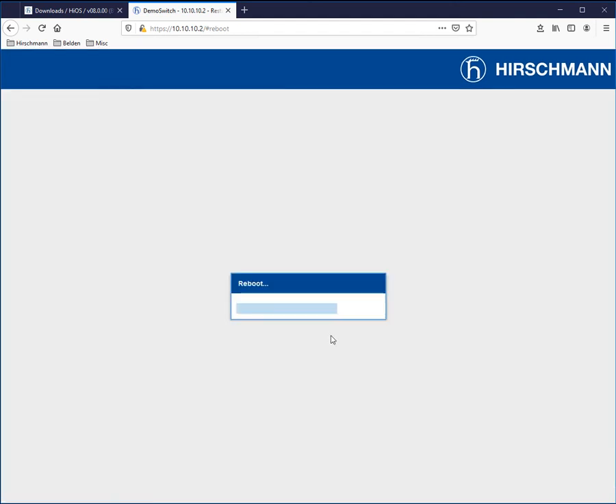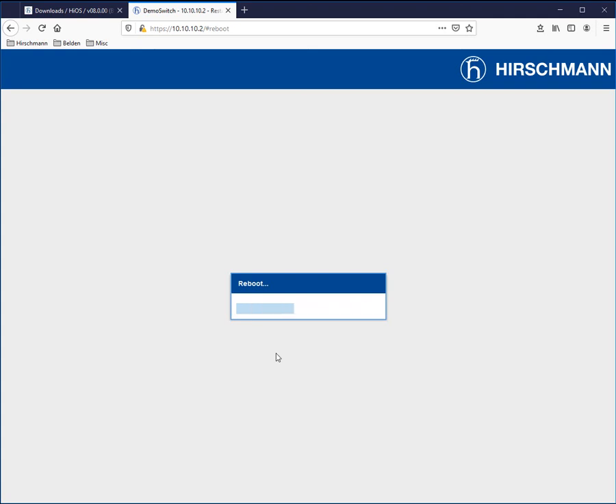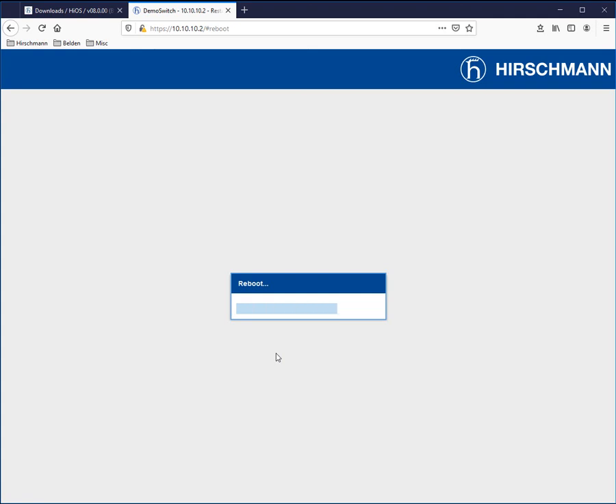So you'll notice the switch is going to go through the reboot. And this will take about two to three minutes because in the process it's also updating the firmware. By it storing the firmware and loading the firmware during the boot, this prevents the switch from accidentally being bricked in the event of a comms interruption during the firmware upload.